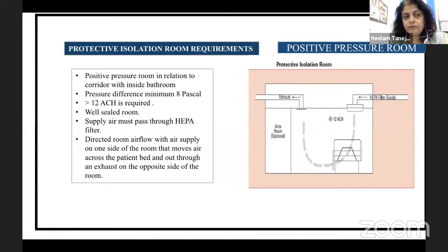Coming to the positive protective isolation room requirement. In this, the air is coming through HEPA filtered air. This is for a bone marrow transplant unit. It is passing over the patient and being exhausted above, not below. A minimum of 12 air changes are required, and the pressure difference should be 8 pascals.